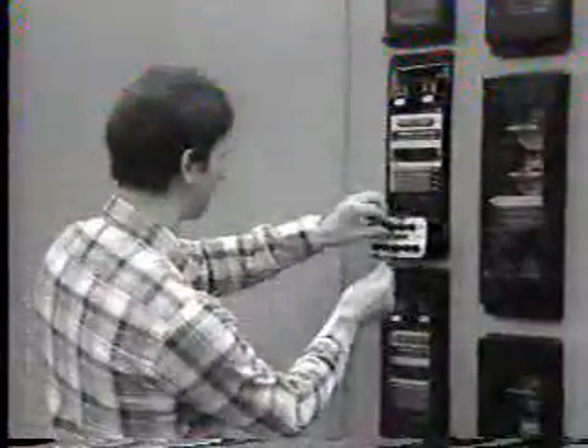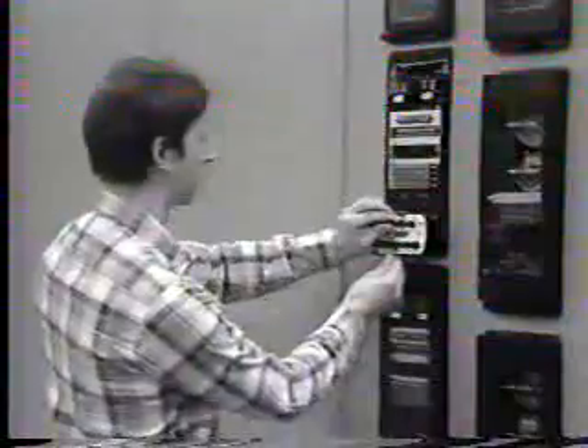One of the problems that concerns operators and relay personnel is how to measure the level of performance of the relays. Will the protection system work properly when needed? Regular maintenance and testing is vital so as to assure us that the relays will operate when required to do so. But this is not enough. We also need to know how the relays actually performed during incidents of actual fault conditions. After any incident, it is essential that all of the relevant information be recorded and analyzed. This analysis will require good coordination and cooperation between both operations and relay departments.